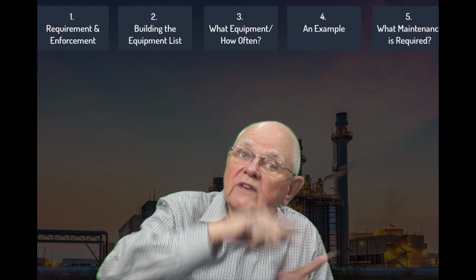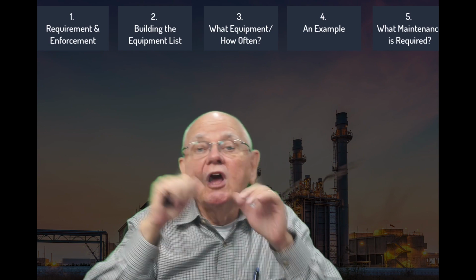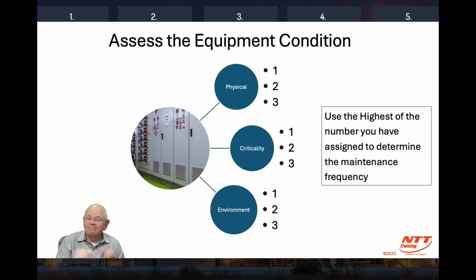Whether I use the NFPA 70B standard or the NETA standard, it still boils down to the same thing: I have to look at the physical condition of my equipment, the criticality of that equipment, and its operating environment. From there, I can assess and come up with what I call the equipment condition, and then determine how often I have to do my work on it.